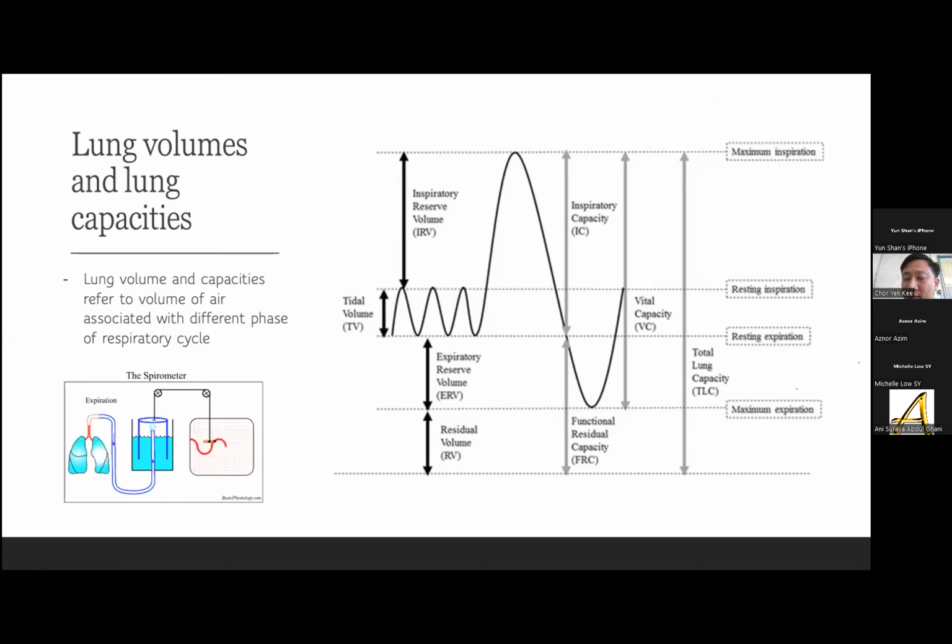You might see a good set pressure and tidal volume, but the patient just doesn't ventilate well. Although the machine shows a good tidal volume, the patient doesn't seem to receive the appropriate tidal volume. That's the problem: the machine is also calculating the distension of the tubing. You get what I mean?